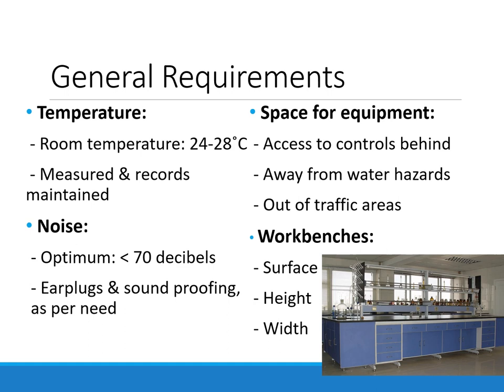Noise: the optimum noise in the working area of a laboratory should be less than 70 decibels. Ear plugs must be provided and soundproofing should be done in areas with very loud equipment. Adequate space must be provided for all equipment — they should be placed at least six inches away from the wall so that controls behind the equipment may be accessed easily, and they should be kept away from water hazards like hand washing sinks and out of traffic areas.